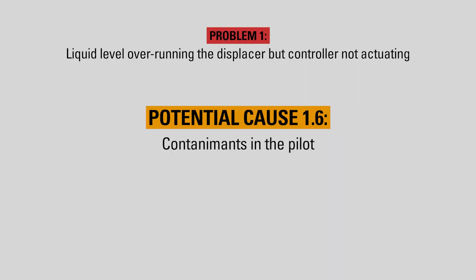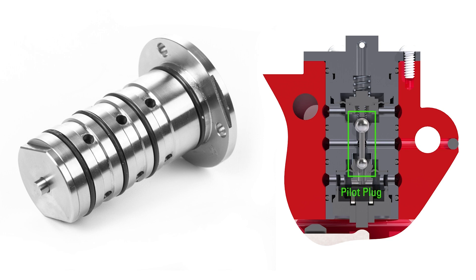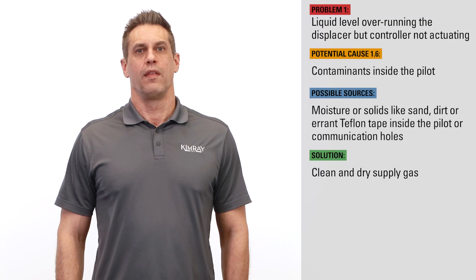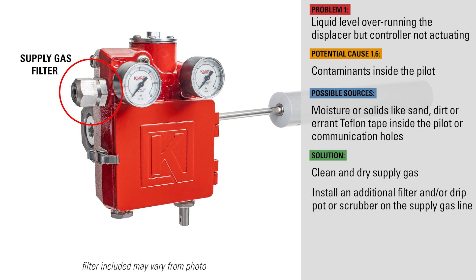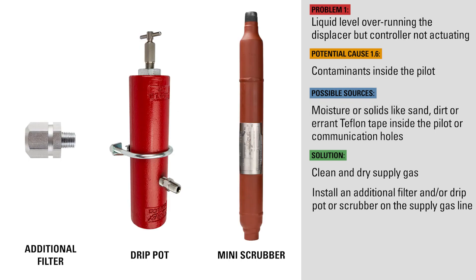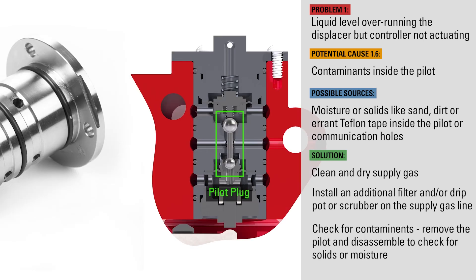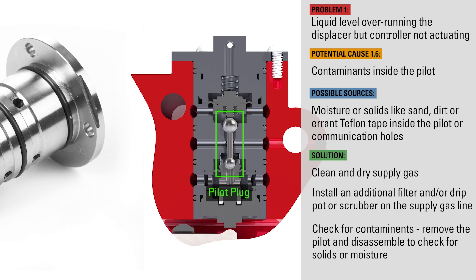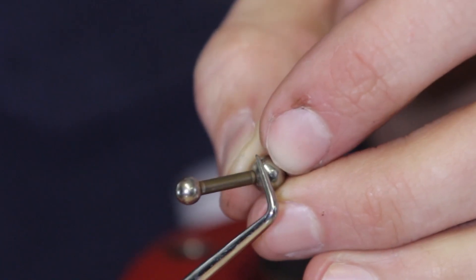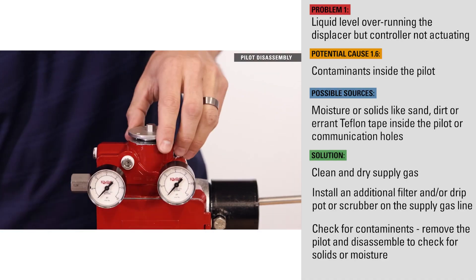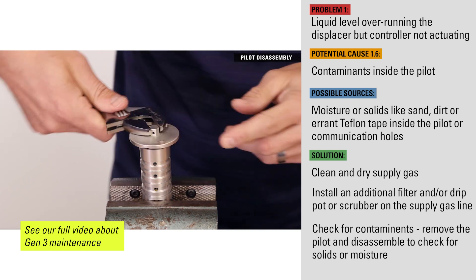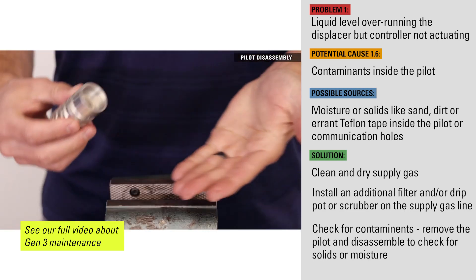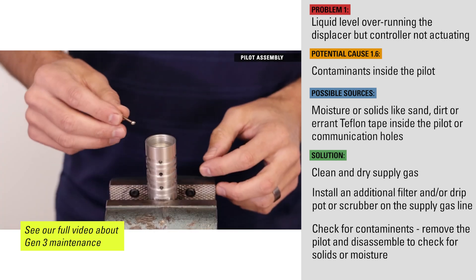Moisture or solids like sand, dirt, or errant Teflon tape inside of the pilot or communication holes inside the casting could prevent the controller from actuating. The supply gas should be clean and dry. The Gen 3 comes with a supply gas filter, but if that's not enough, we recommend installing an additional filter and/or drip pot or scrubber on the supply gas line. The pilot plug inside allows for very precise control and low emissions, but contaminants can prevent the pilot plug from moving or restrict full range of motion. To check for contaminants, remove the pilot from the controller, disassemble, check for any solids or moisture, and clean and dry the components before reassembling.